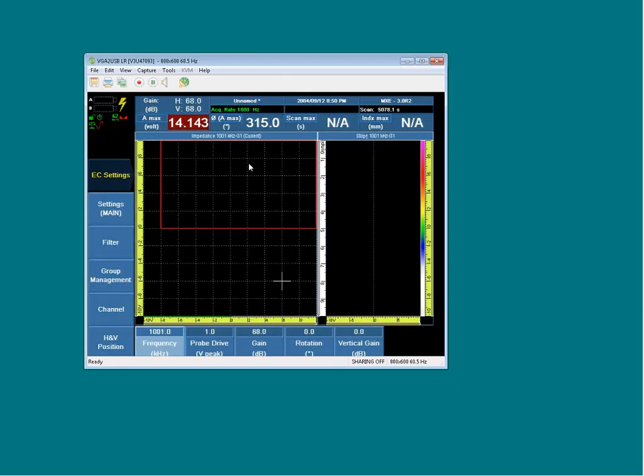All right, so I'm going to start this presentation with the probe on the stainless steel 316 standard. Right now I have the probe with the encoder attached with a flat wedge on it, and I just put the probe on the standard with the shim on, and I'm basically going to null the instrument. That says balancing. It's basically calculating the good material, and then what I'm doing is lifting that probe up, so up and back on the standard, and there's a kind of display erase on the screen so the display doesn't get too crowded. That's why we lose the signal once in a while. But what you get to see there is the 32 traces, the 32 coils all together in the same impedance plane, shown just like conventional eddy current.